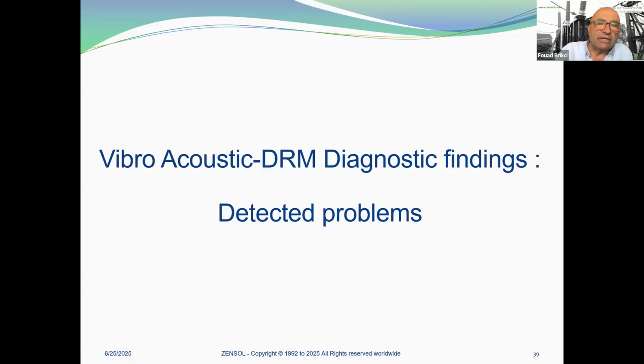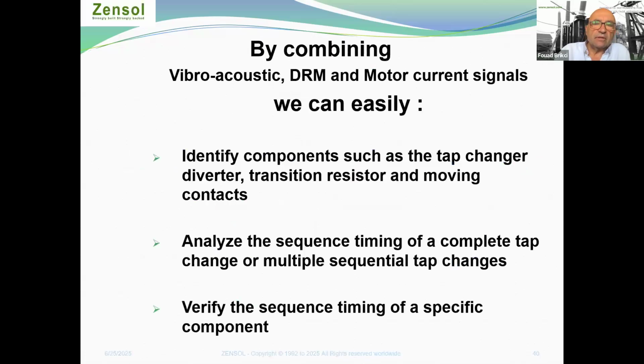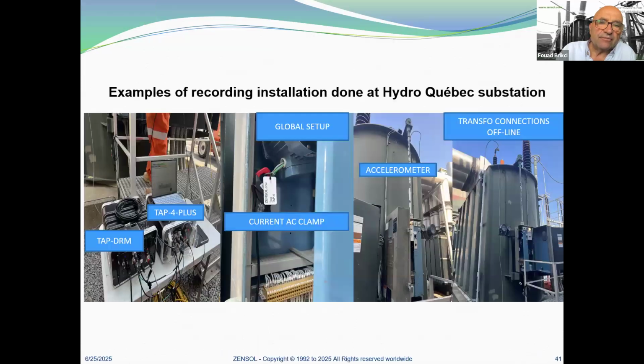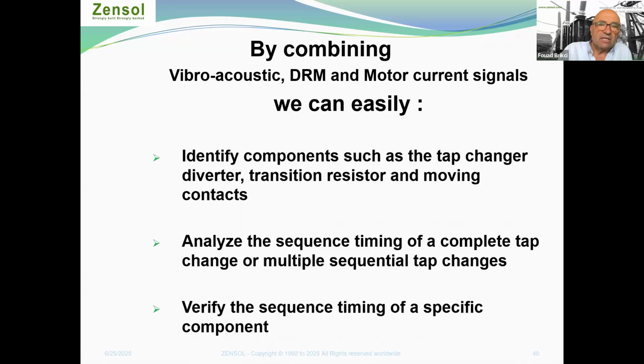Vibroacoustic DRM diagnostic: detected problems. In fact, what we do is just add the DRM to the vibroacoustic and the motor current. By combining vibroacoustic, DRM, and motor current signals, we can easily identify components such as the tap changer diverter, transition resistor, and moving contacts, analyze the sequence timing of a complete tap change or multiple sequence tap changes, and verify the sequence timing of a specific component.